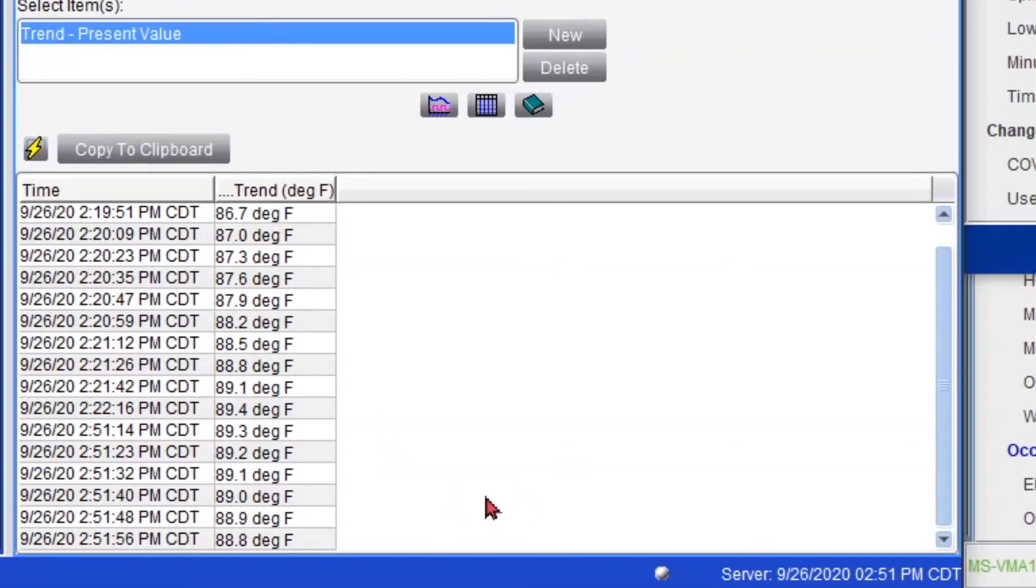So right here you can see if you were to calibrate a room temperature sensor, you'll have a more precise feedback when you're reading your sensor and changing your offset value. Because you can calibrate it by the 0.1 precision.